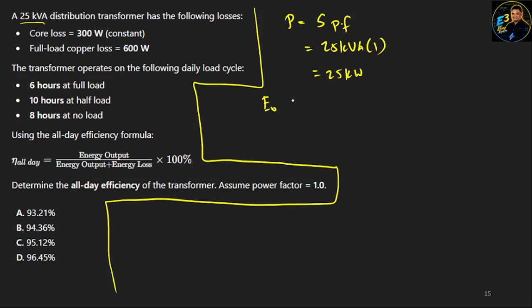For 6 hours, yung ating transformer is operated at full load, which is 25 kilowatts. Plus, sa 10 hours, it is operated at half load, so kaya half ng 25 is 12.5. Ito hours, ito kilowatt, so magiging kilowatt hour po yung unit natin.